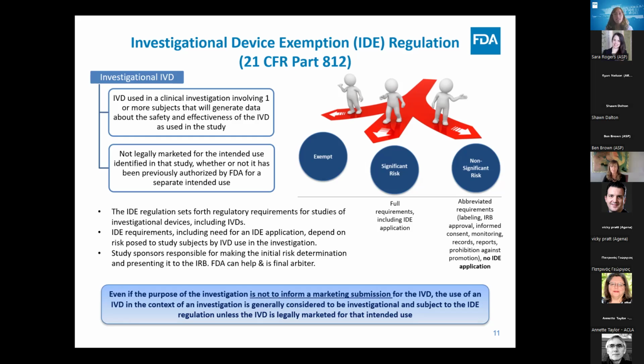So IDE requirements, including the need for an IDE application, depend on the risk posed to study subjects by use of that specific investigational device in the investigation. And only significant risk studies require an approved IDE application prior to the study initiation. Those studies with non-significant risk devices must still comply with certain abbreviated requirements pertaining to labeling, IRB approval, informed consent, monitoring, records and reports, and there are some prohibitions against promotion.